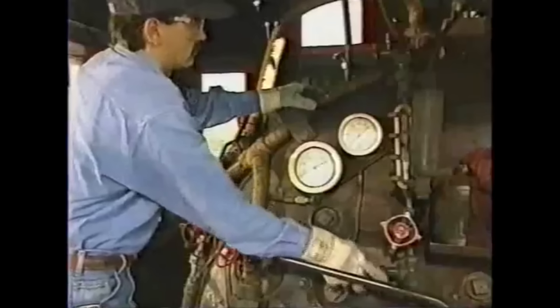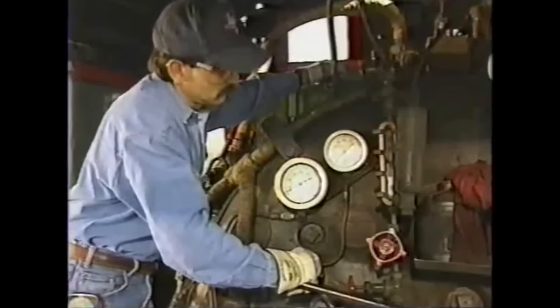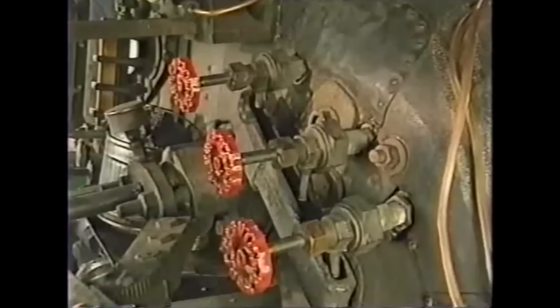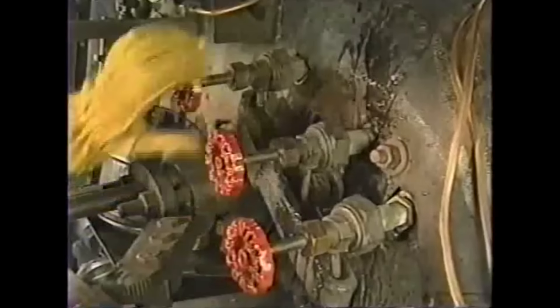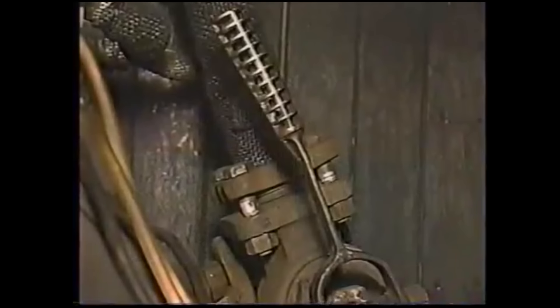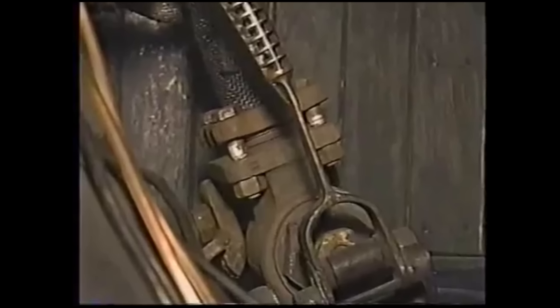Only the owner of the Gettysburg Railroad — the engineer's father — demonstrated the correct method of blowing the glass down. All Gettysburg Passenger Service employees had been taught by the engineer, and no one confirmed that he also tested the gauge cocks when blowing down the water glass, as required by regulations. The NTSB therefore concluded that the firemen had not been properly taught how to blow down the water glass or test the gauge cocks, reflecting a lack of an effective training program at the Gettysburg Railroad. The water injector, which helps flow water from the tender into the boiler, was also non-functional because the wrong metal disc was installed, making water flow to the boiler difficult.